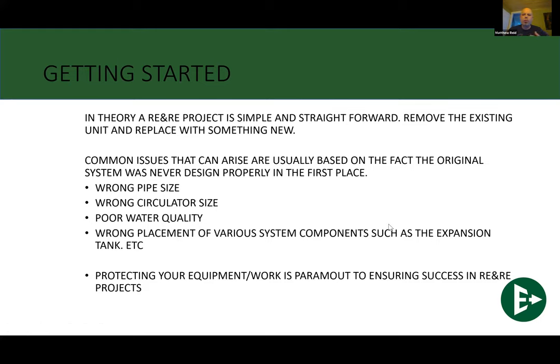Basically, removing a boiler and putting in a new boiler sounds super simple. You take out the old, put in the new. Sounds simple enough. But these are things that we come across out there in the field a lot that can arise. It's usually based on the fact that the original system was never designed right to begin with. Maybe they've been pumping into the expansion tank for years and years and never had flow there. Maybe the piping was always too small. Basically, the main issues that I see when I go to job sites are the wrong pipe size and wrong circulator size.